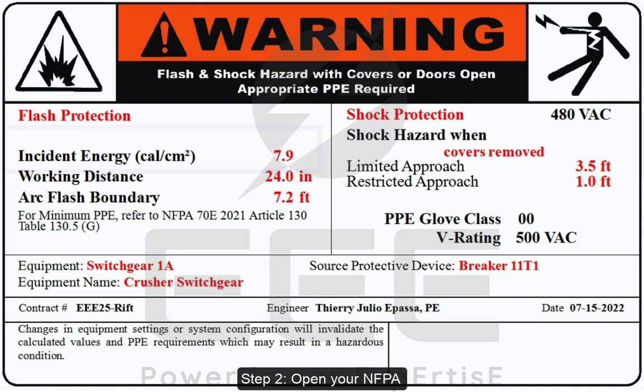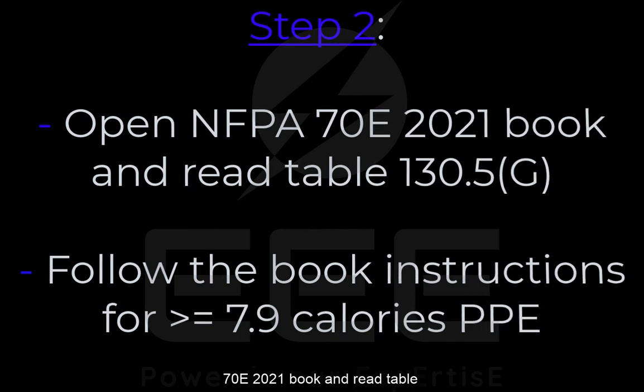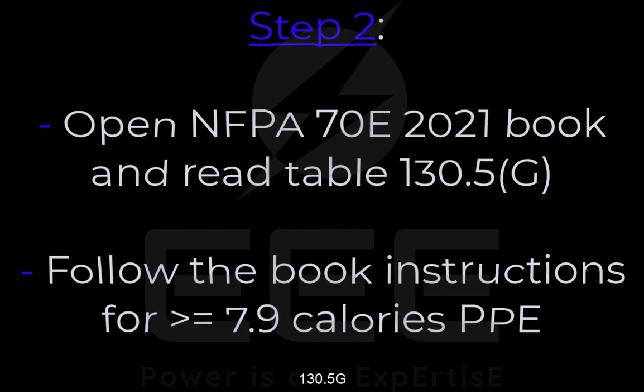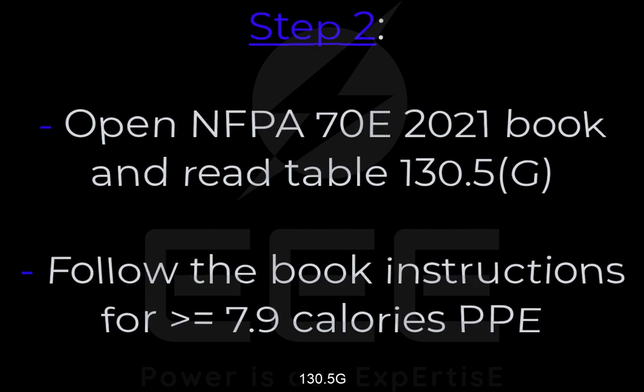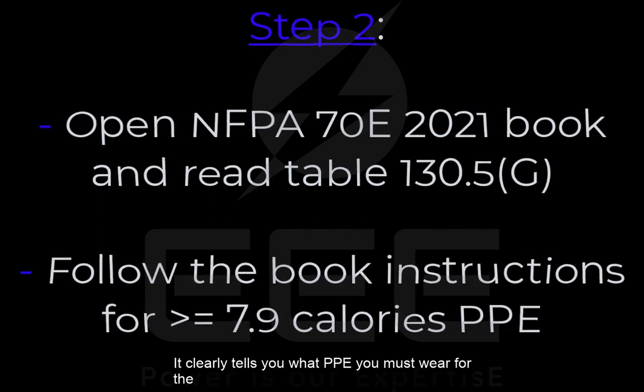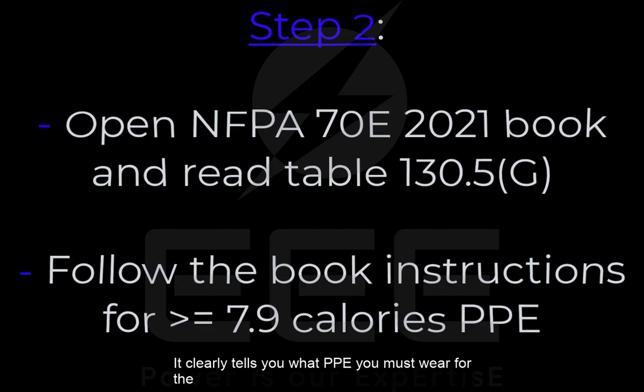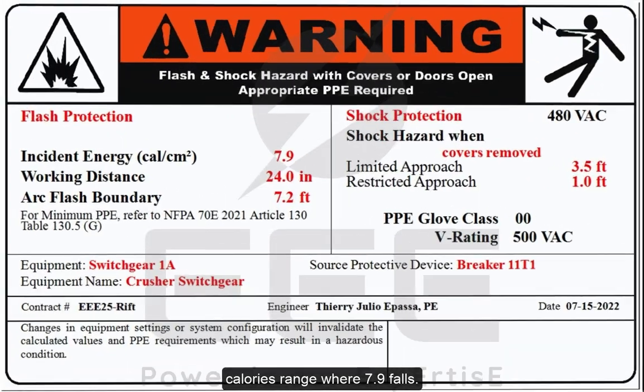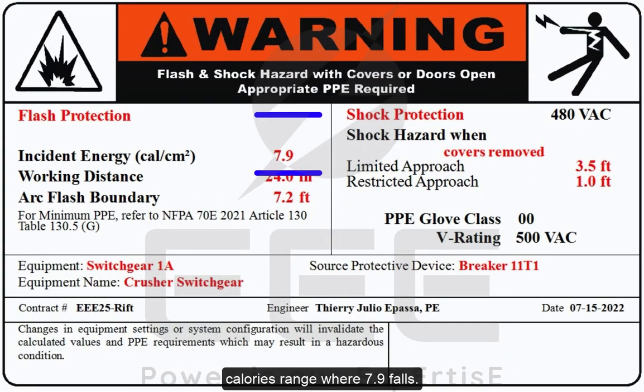Step 2. Open your NFPA 70E 2021 book and read Table 130.5G. It clearly tells you what PPE you must wear for the calorie range where 7.9 falls. Wear that PPE.